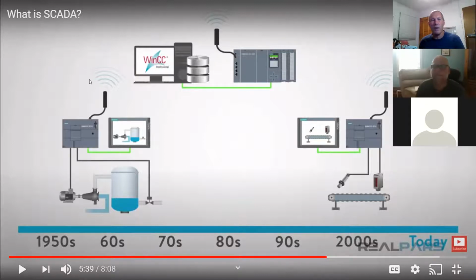So you have the ability to monitor everything, which is great for forecasting what your future is going to be like - do I need to add another substation because one's getting overloaded so much? And you're able to control - he's able to send signals back to the substation to control any points he has set up for SCADA to operate.